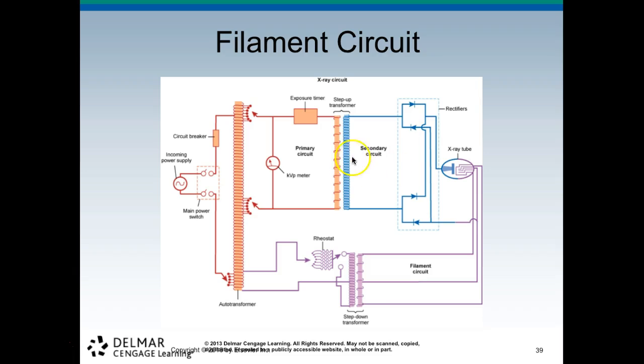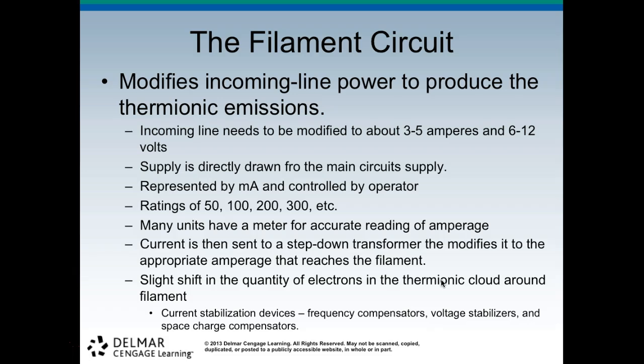So with our filament circuit now, we've covered the primary circuit and the secondary circuit, and now we're going into the filament circuit. It modifies incoming line power to produce thermionic emission. That's the goal. The incoming line needs to be modified to about 3 to 5 amperes and 6 to 12 volts. The supply is drawn directly from the main circuit supply, represented by mA, and controlled by the operator.